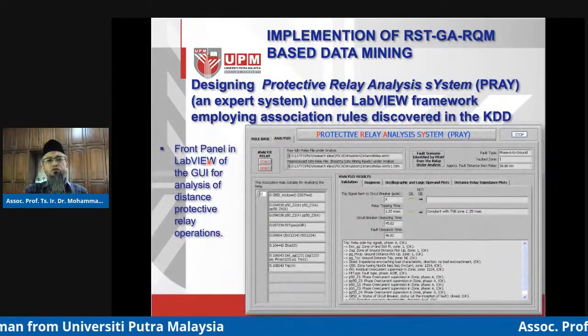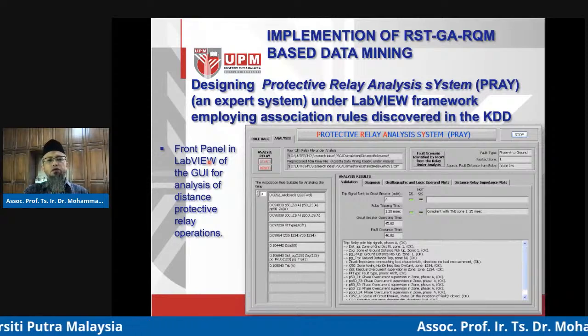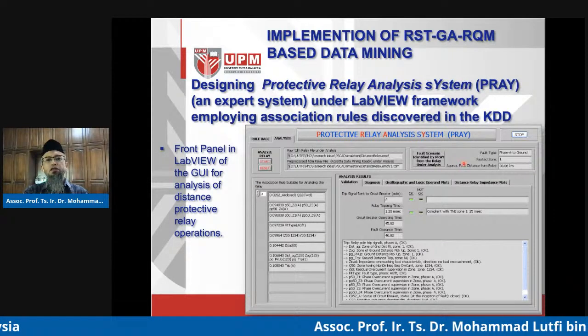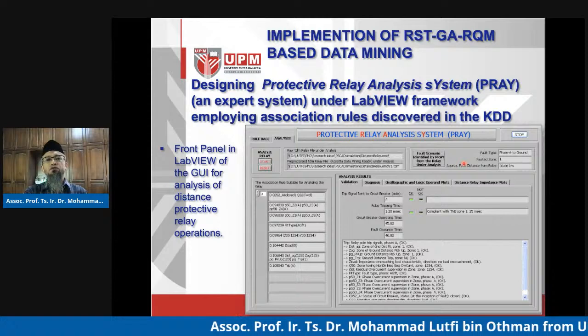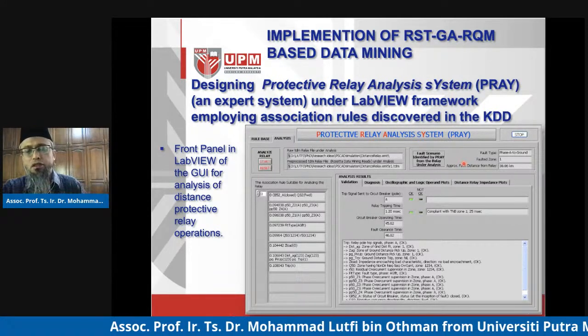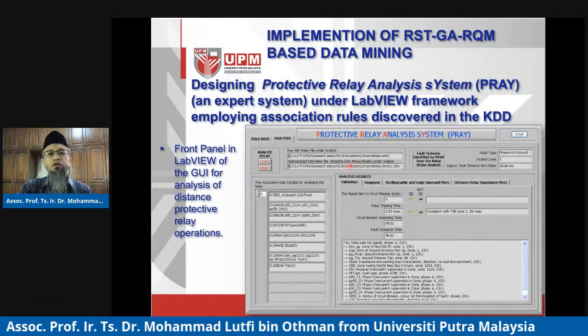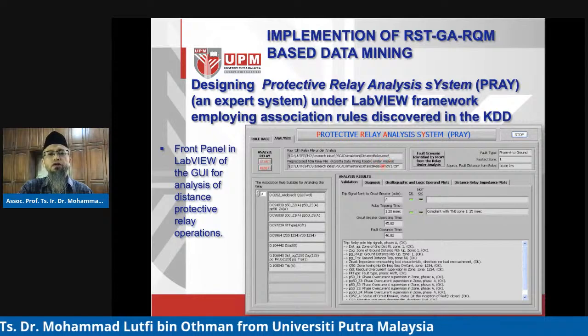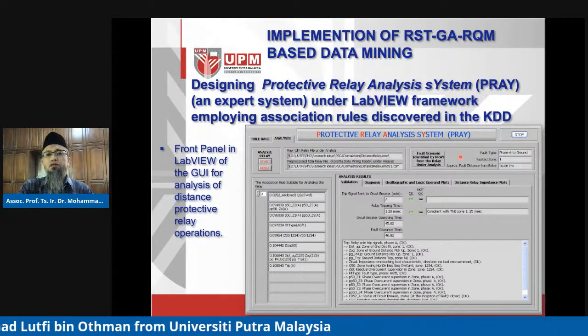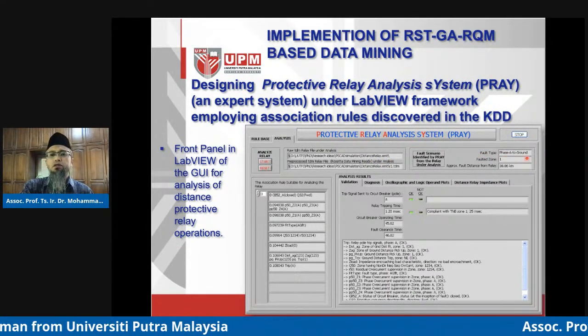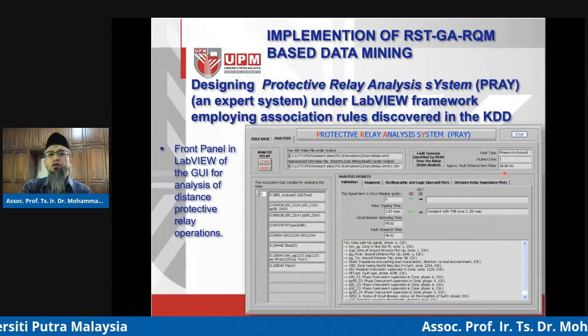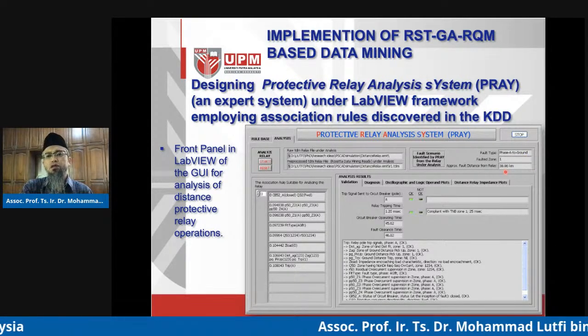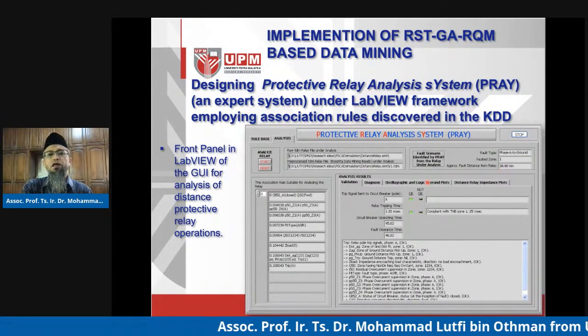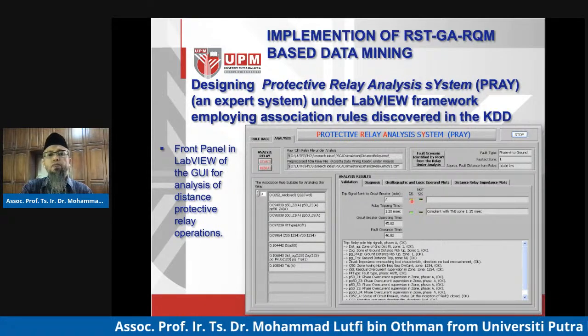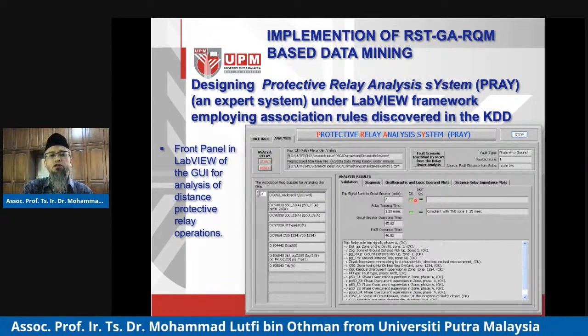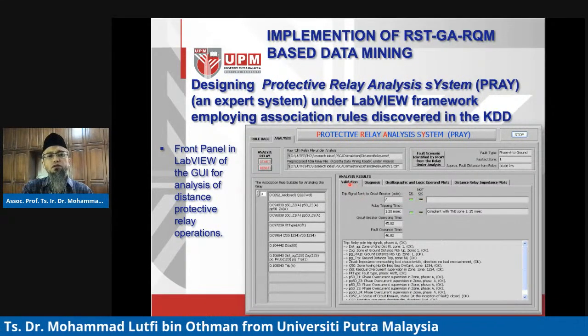Next, we want to validate the rules with the relay we want to test on, to see how well the unknown relay has performed. We link to the unknown relay's file, and it was discovered that a fault has occurred, a phase A to ground fault, in zone number 1, scoring somewhere around 38 to 39 kilometers away from the distance relay. And it's rightly so, the relay has successfully operated and is validated.